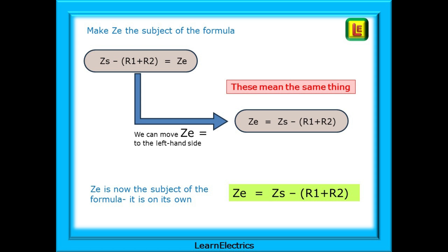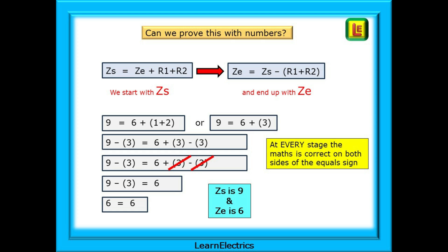We can tidy this up a little. It's common practice to put the subject — the number that we want to know — on the left-hand side. So we can move ZE equals over to the left to give us ZE equals ZS minus (R1 plus R2). Can we prove this with numbers? We started with ZS as the subject and ended up with ZE as the subject. Let's say ZS equals 9, ZE is 6, and R1 plus R2 is 1 plus 2. The equation balances: 9 on the left equals 6 plus 1 plus 2 on the right.